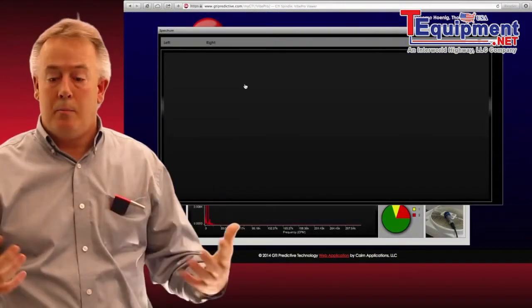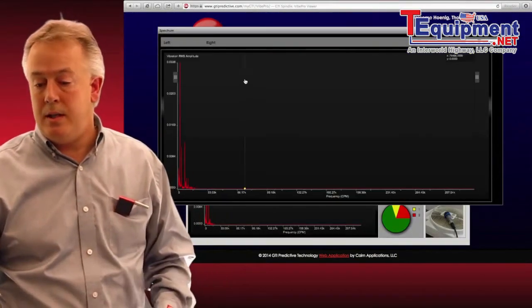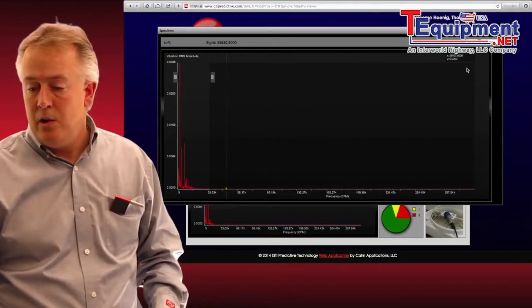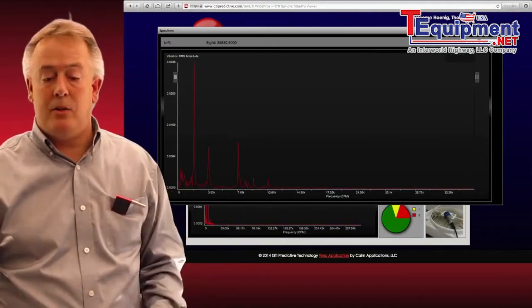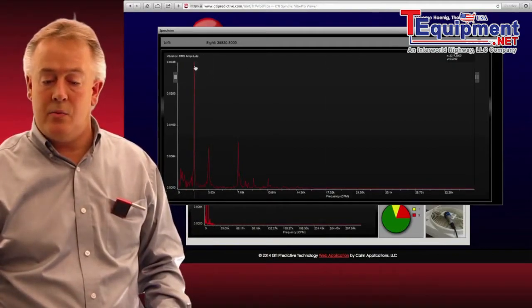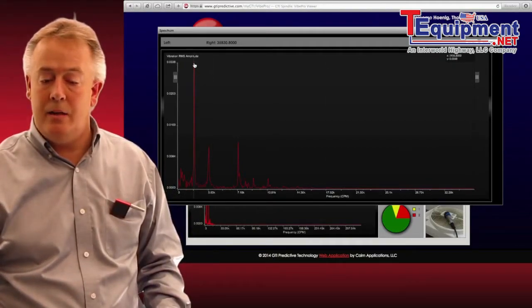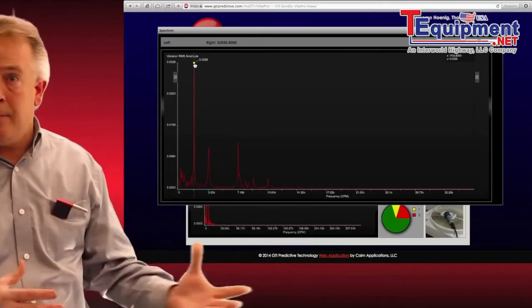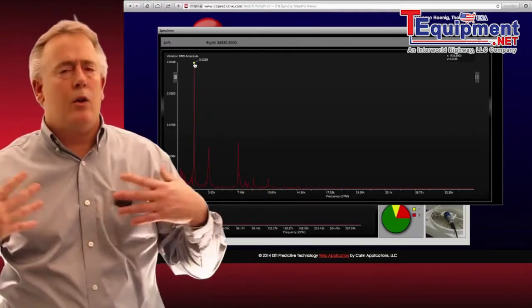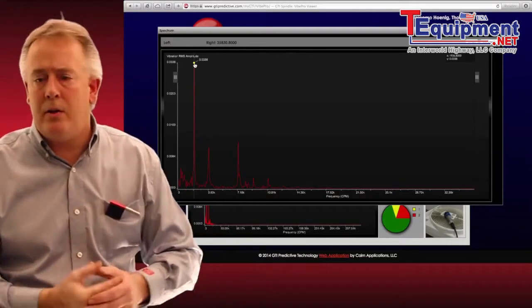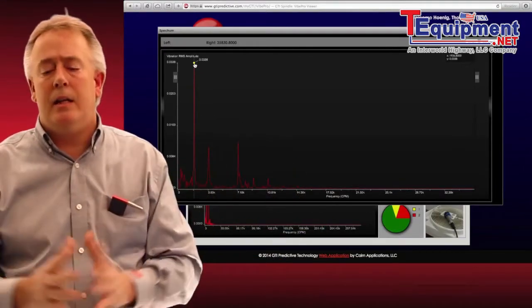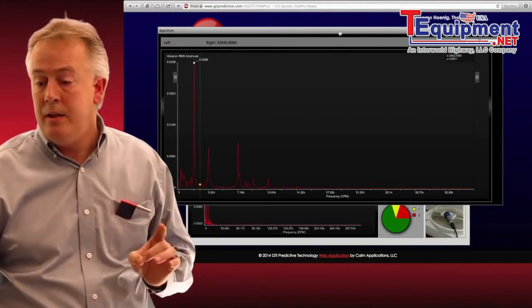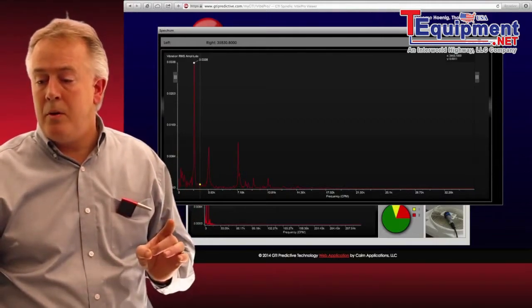I can look at a large spectrum view for heavy-duty post-processing. I can bring the wings over, regraph it, pull that spectrum out to look at the one-times running speed peak, click on that marker to see its amplitude and frequency. We can also look for bearing markers and RPM markers — all of that is heavily loaded into this post-processing tool.